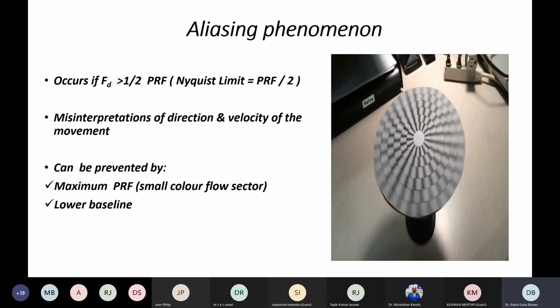For example, if the RBC is moving away from the transducer and we are not using the correct frequency of the piezoelectric crystal, the aliasing will show erroneously that the RBC is moving in the opposite direction. Whereas it is actually moving away from the transducer, it will be seen as moving towards the transducer. And we will have a completely wrong interpretation of the particular direction and velocity of the Doppler movement of the RBC. So how can we prevent aliasing?